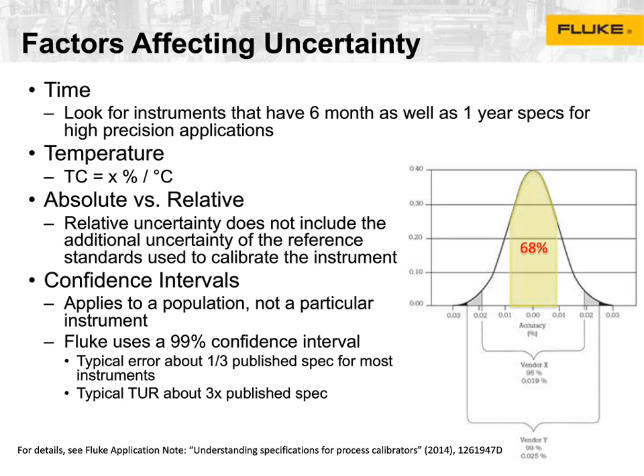So you can see that they are both on this curve, and vendor X here is quoting a 0.019% error, while vendor Y is quoting a 0.025% error because they are using a different confidence interval. Just to save you the trouble of having to ask us, Fluke uses the more conservative 99% confidence interval.